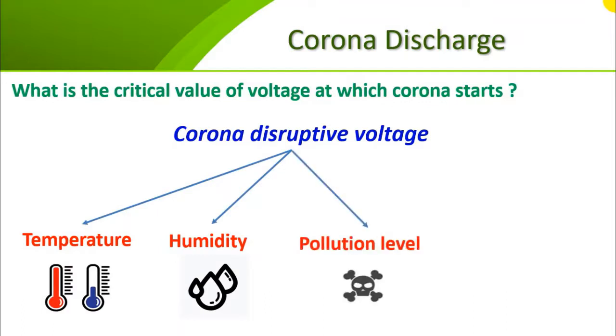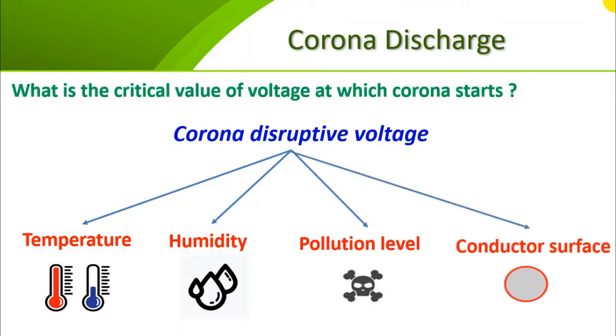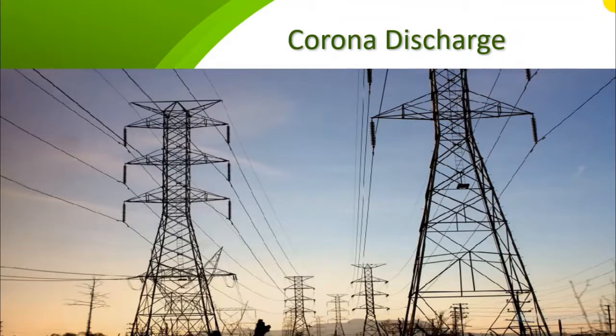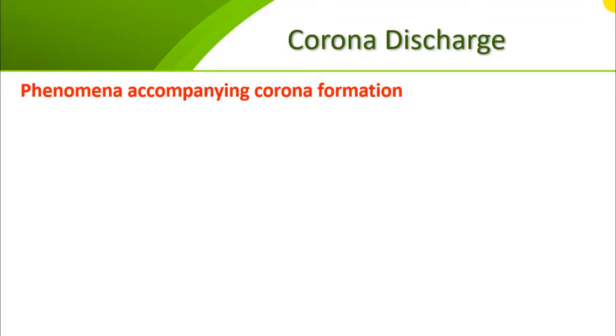Pollution level contributes to the formation of corona, since polluted conductors increase the concentration of the electric field on their surface. Also, conductor surface is a significant factor that affects the corona disruptive voltage, as a smooth and clean conductor is less subject to corona formation than a rough conductor. Also, there is another thing you should know: corona effect is generally seen in transmission lines carrying 300 kilovolts or higher. So if you are passing by an 11 or 33 kilovolt line, you may not see the corona effect there. So now let's understand the bad effects and disadvantages of corona when it happens.